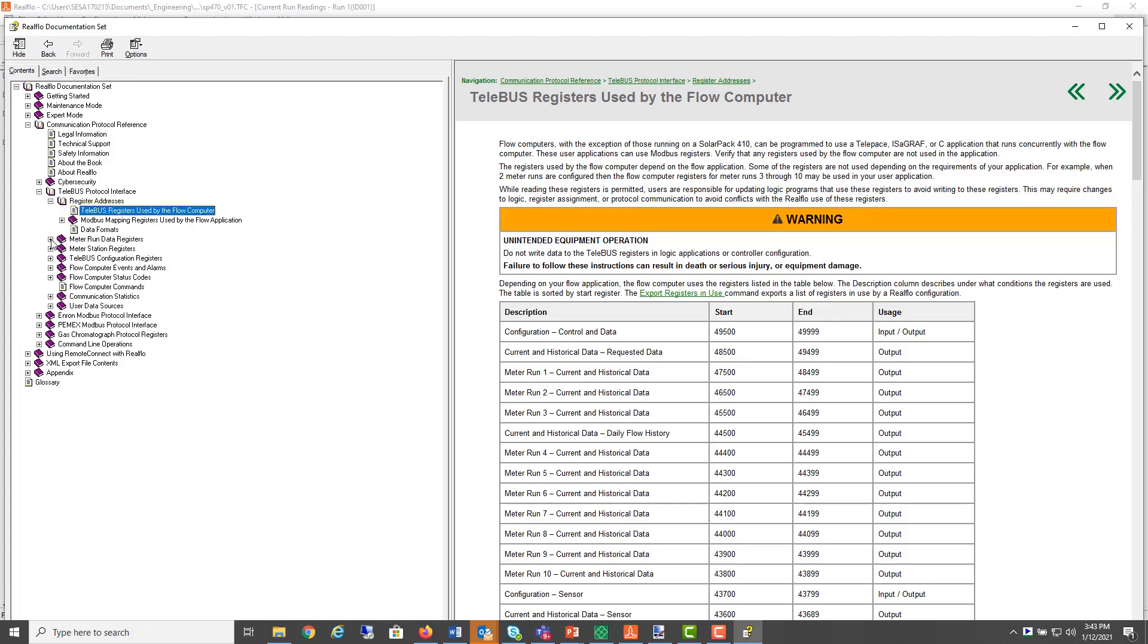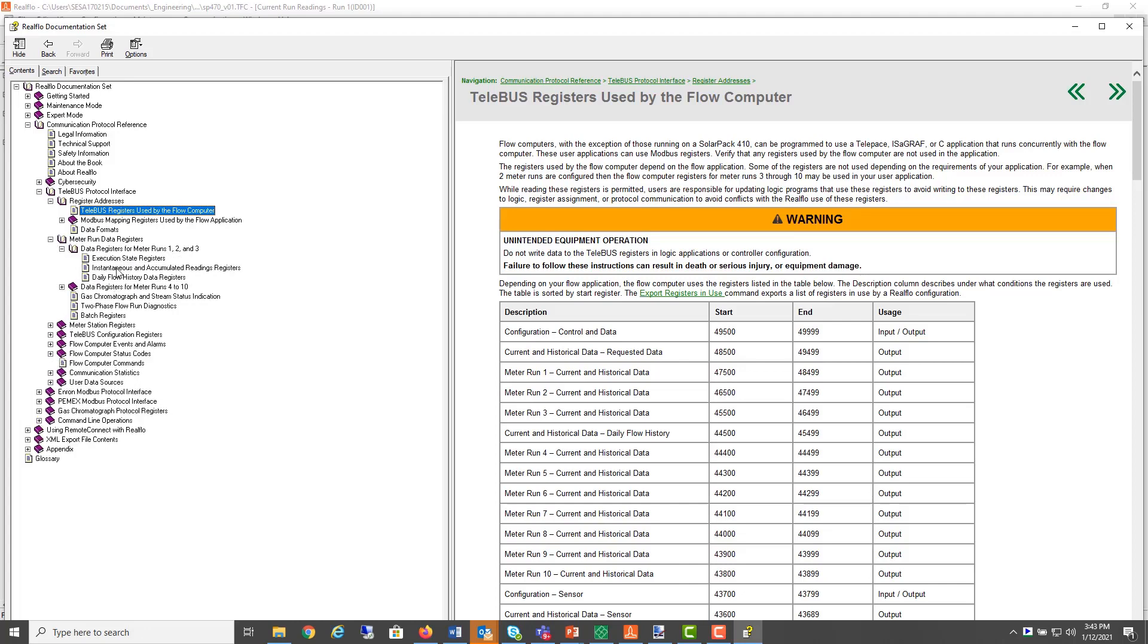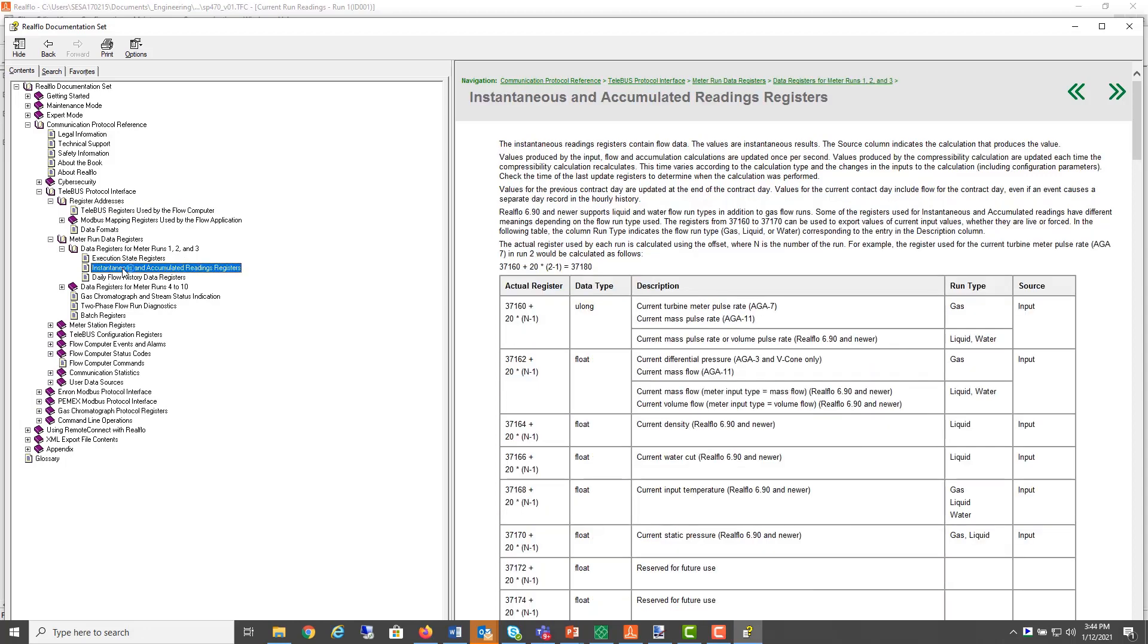I'm interested in meter run number one and the instantaneous readings. For example, let's look at the temperature and static pressure. These are located at a floating point register 37, 168 and 170.